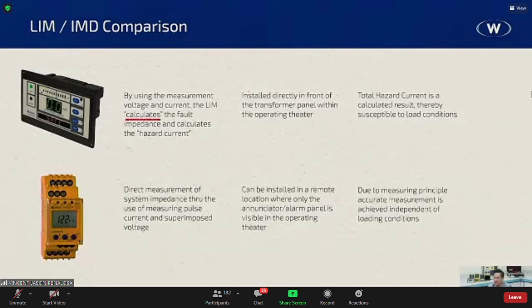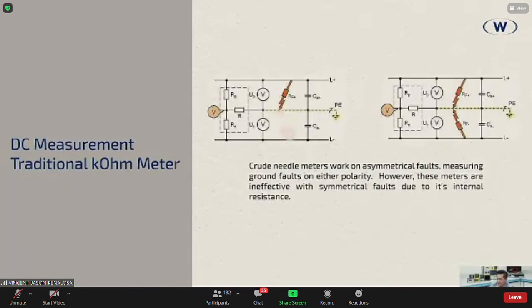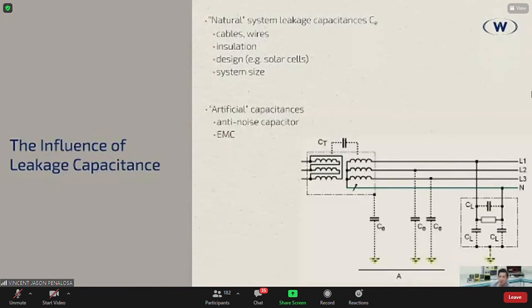So it's gonna have to be a clean room. You're gonna have to open up panels and take out the transformer, clean them and dry them out, and sometimes even purge them with nitrogen or whatever. And that becomes a pain in the neck, right? The main reason why it's directly mounted in front of the panel is because of, I'll go back a couple of slides, cables and wires, the distance and length of cables and wires. It cannot handle longer distances than that of right in front of the panel.